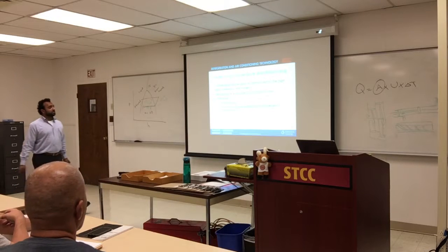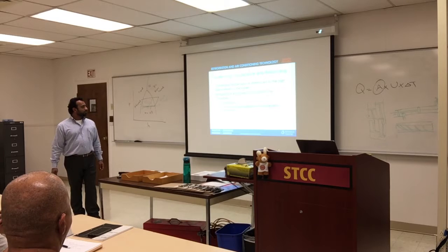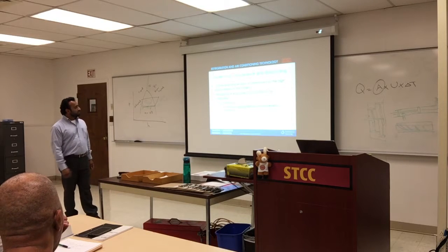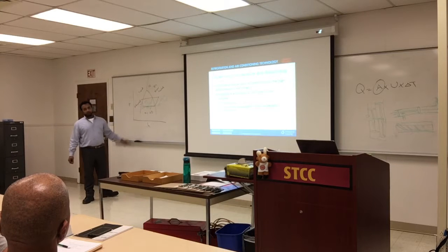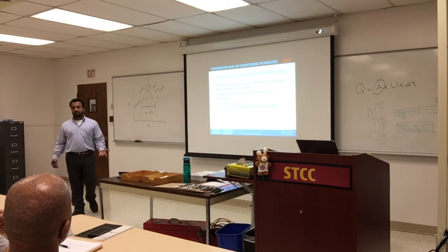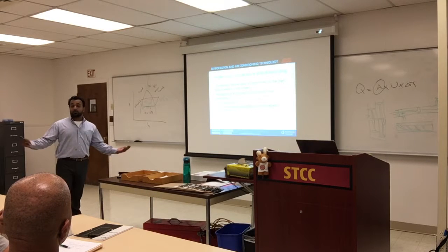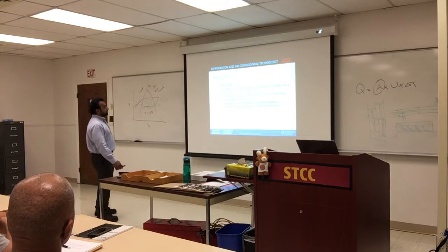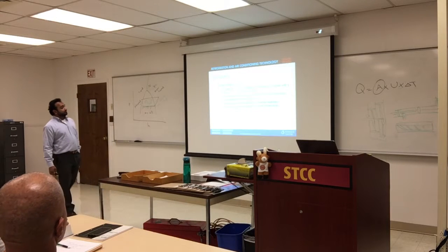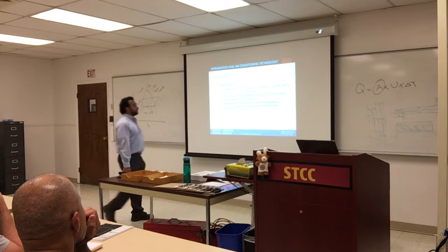So condenser temperature is determined by the high side pressure of the system, and the refrigerant is subcooled at the output of the condenser. And subcooling again is going back to the beginning of the curve. We're cooling something that's already liquid, so it just has some heat that it wants to absorb because it's lacking heat. So air cooling systems are designed to operate at a minimum of 10 degrees of subcooling.